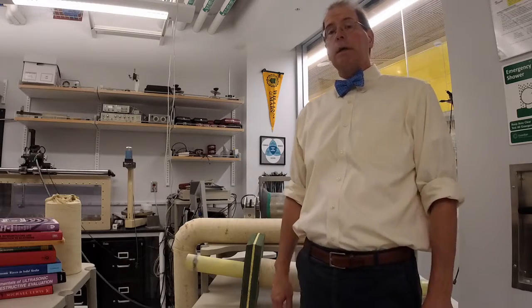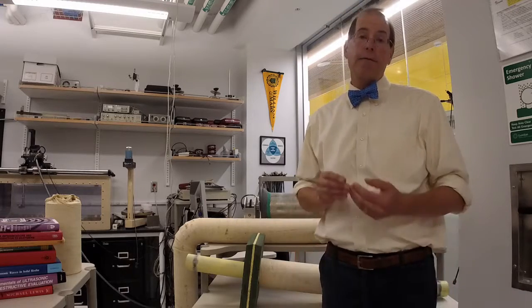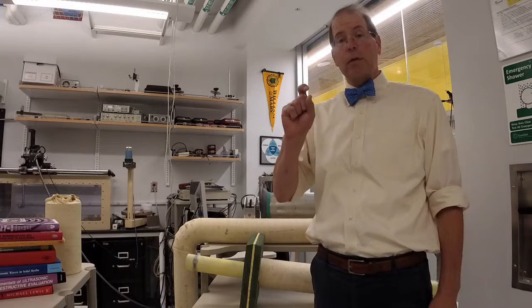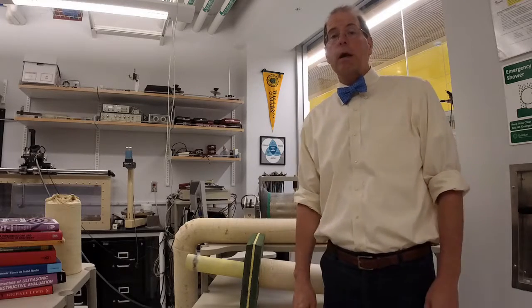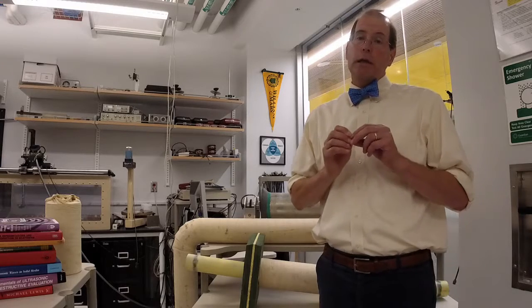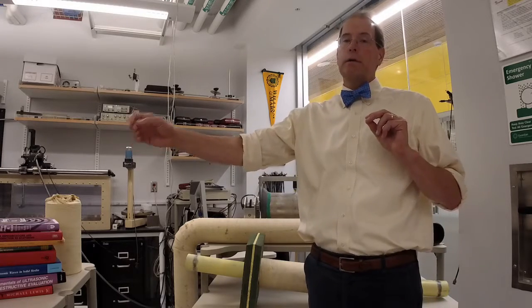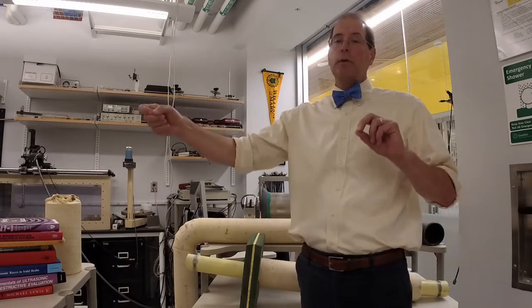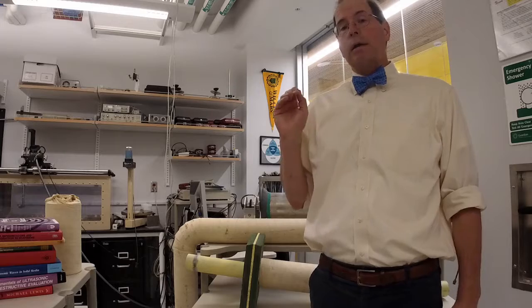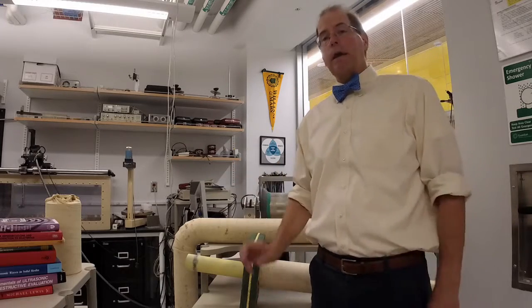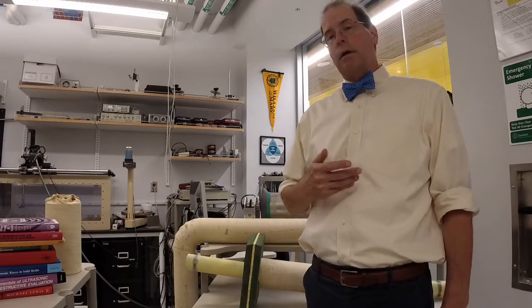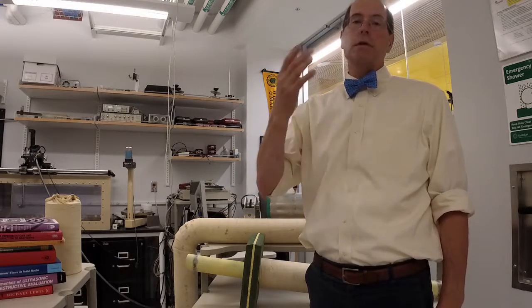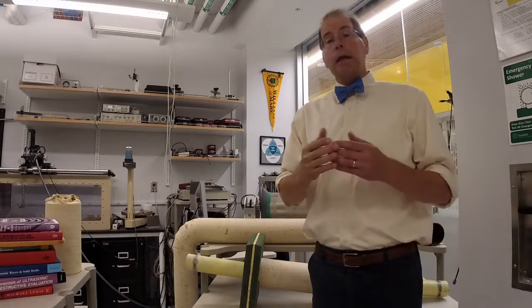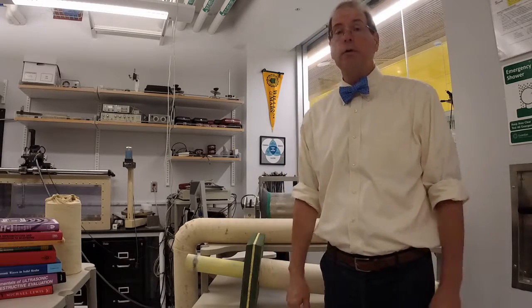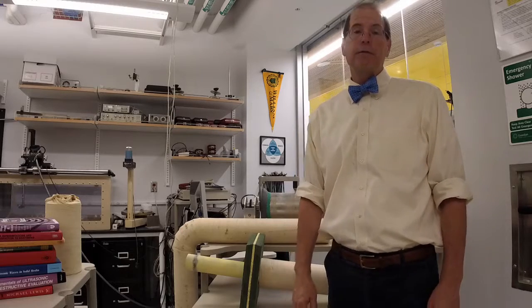One important thing about the ultrasonic guided waves is that how fast they go depends on the thickness of the wall. So if you're trying to find a place where the wall has gotten thinner, you look at the expected arrival time of either the straight traveling waves or the helical modes and compare when they should arrive to when they actually did arrive. That difference in arrival times allows you to map out the slowness, which the Lamb wave dispersion curves let us correlate back to the thickness of the pipe wall. So helical ultrasonic tomography allowed us to make maps of the thickness of the pipe wall.